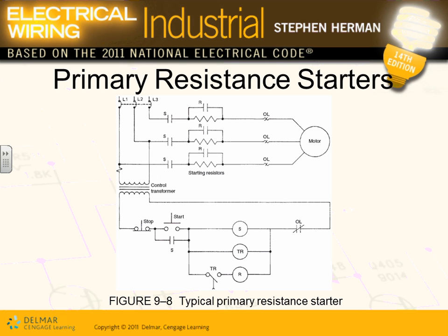So, Jeff, my friend, here's how they do a resistance starting motor. Guess what they do? They take a resistor, they put it in series with the motor. When they energize the motor, the voltage here is 480, but the voltage across the motor for 10 seconds will drop to 240, right? So they lower the voltage momentarily, the inrush goes down, everybody's happy for only 10 seconds. After 10 seconds, bam, they close these contacts, they shunt these resistors and the motor is running at full speed.